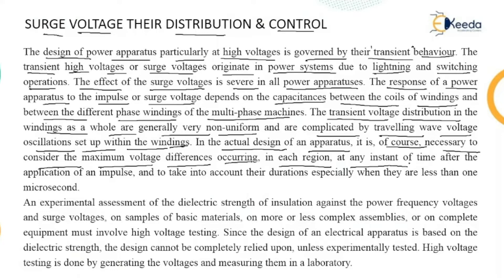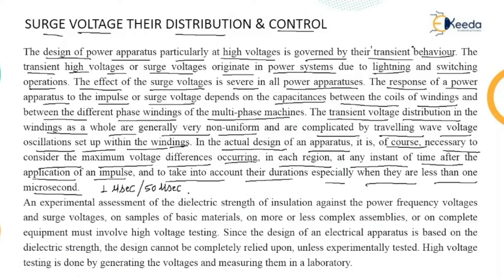In the actual design of apparatus, it is necessary to consider the maximum voltage differences occurring in each region at any instant of time after the application of an impulse, and to take into account their durations, especially when they are less than one microsecond. A surge voltage is represented by a waveform with a rise time and tail time — such as 1 microsecond to 50 microseconds, or 1.2 microseconds to 50 microseconds. The rise time is when the surge rises to its peak value, and 50 microseconds indicates the time for the voltage to reduce from its peak to 50 percent of that value.